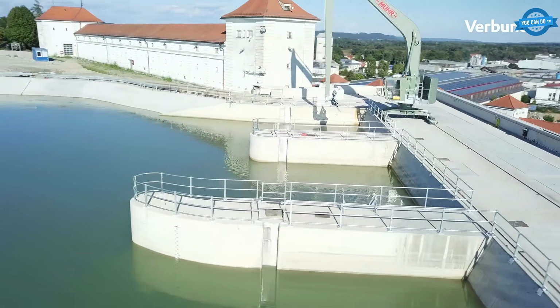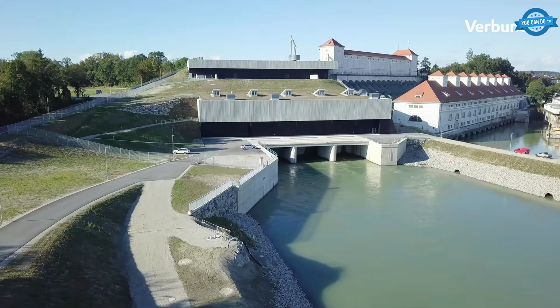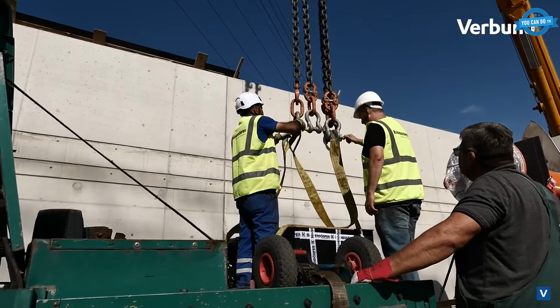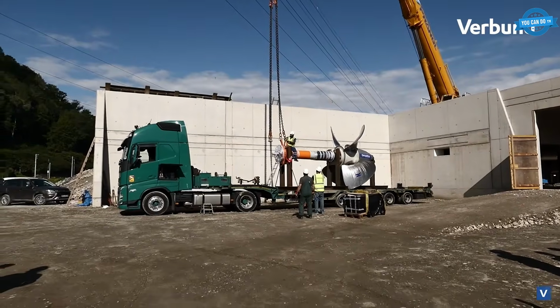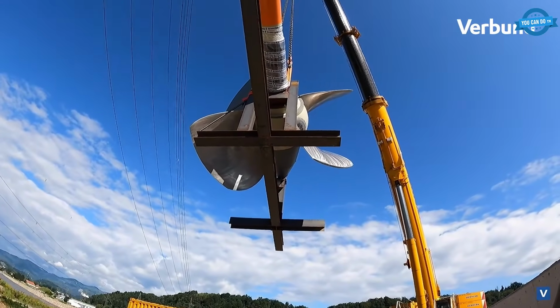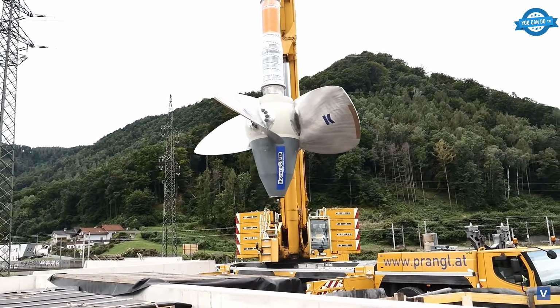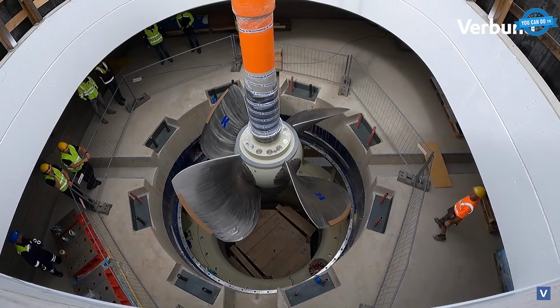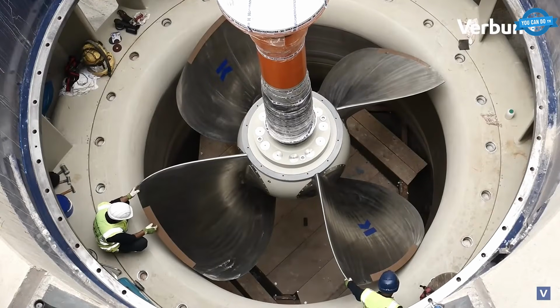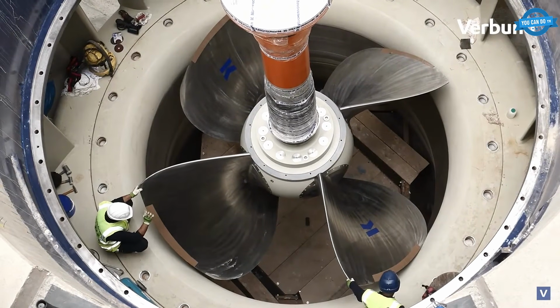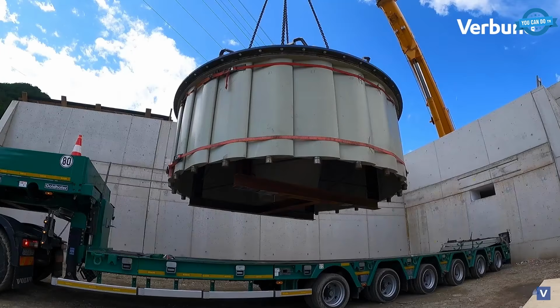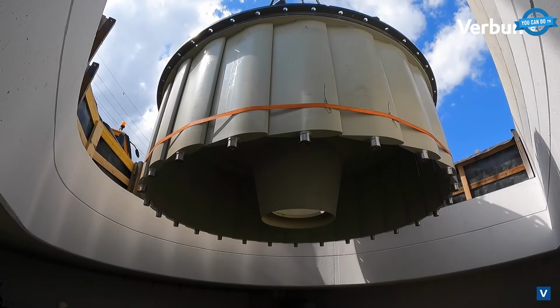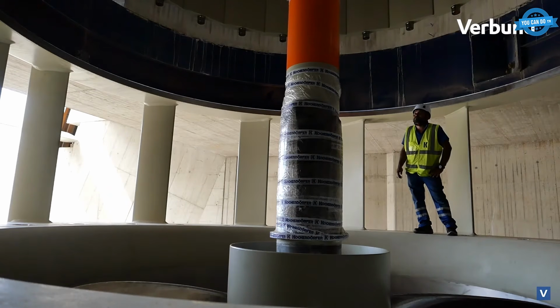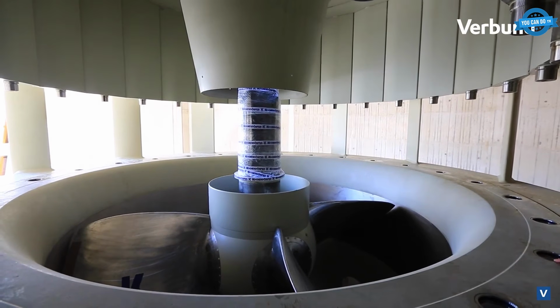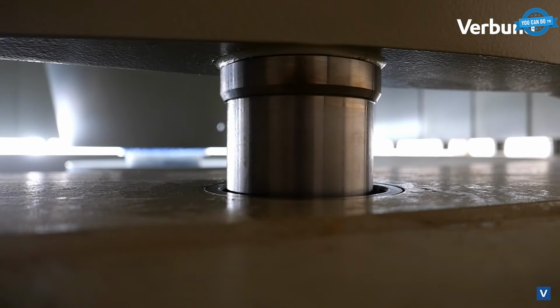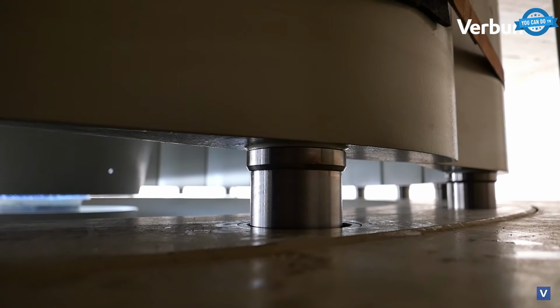historic plant. A 4-meter Kaplan runner travels by heavy truck, gets cabled to a crane, and lowers vertically into a concrete shaft that has waited years for it. Machine sets at the Mur plant go in over August and September. Kaplan turbines 4 meters across, with generators stacked vertically directly above each runner.